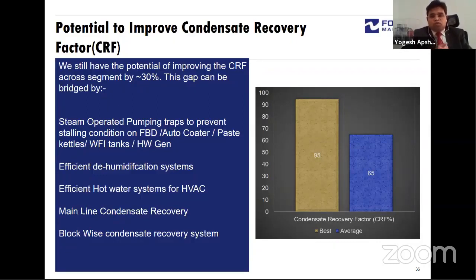In most places, what we have observed is that condensate recovery is typically 60 to 65%. Condensate is recovered only from the major equipment, and not from most of the scattered equipment which is away from the boiler house, because of the fear of the distance. But Forbes Marshall has steam operated condensate recovery systems which can recover the condensate from any point.